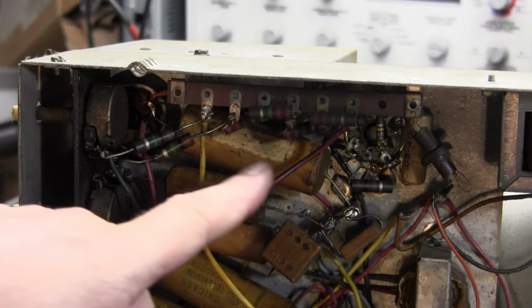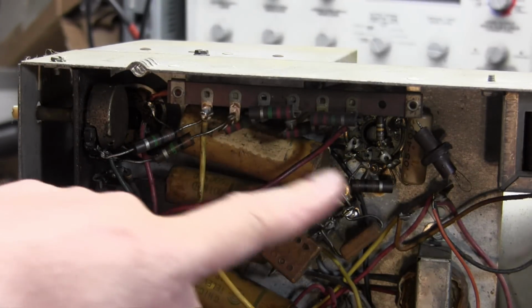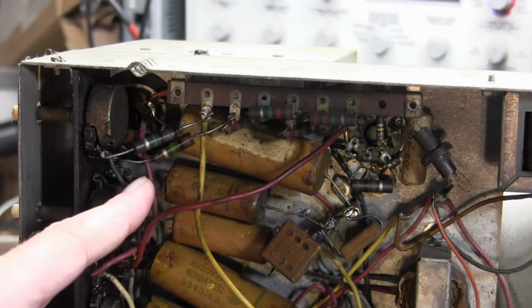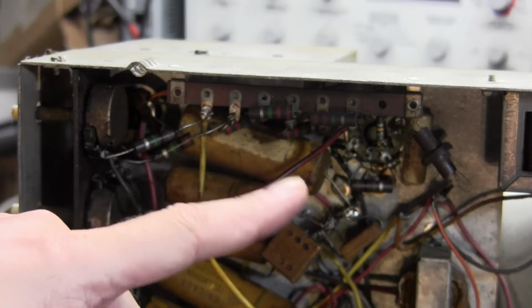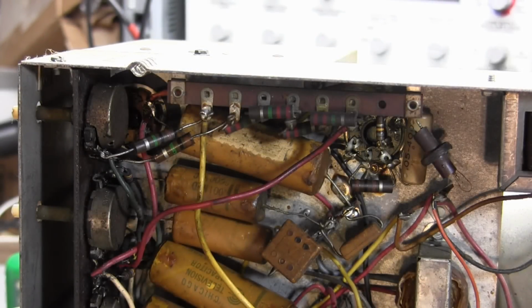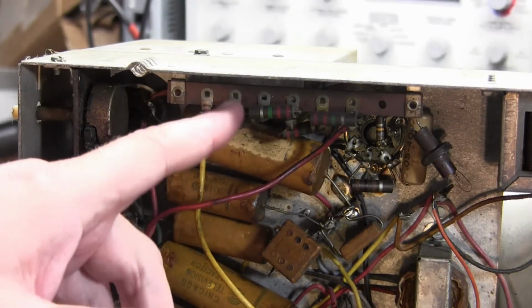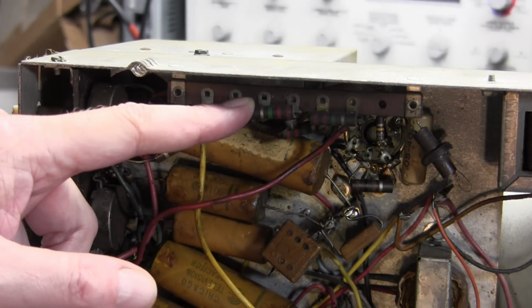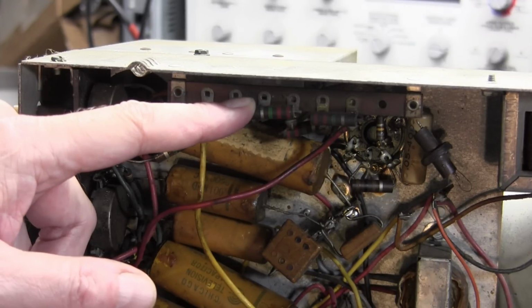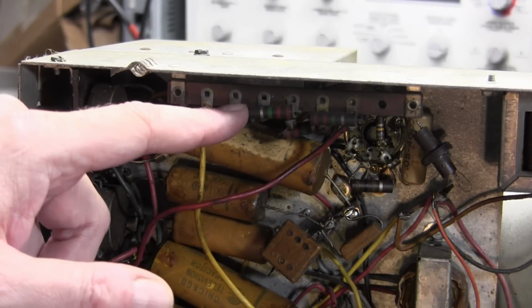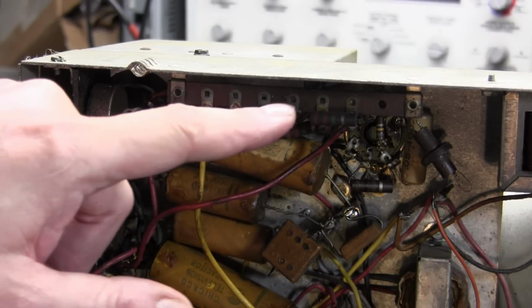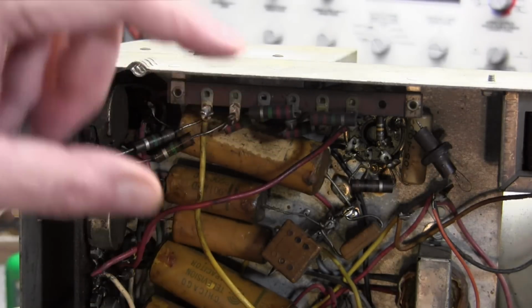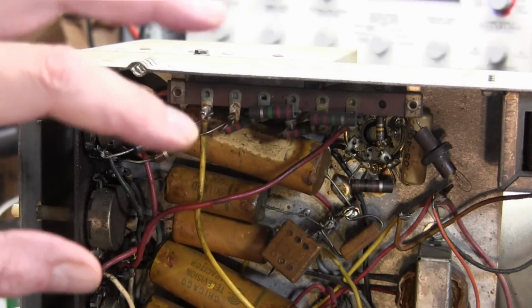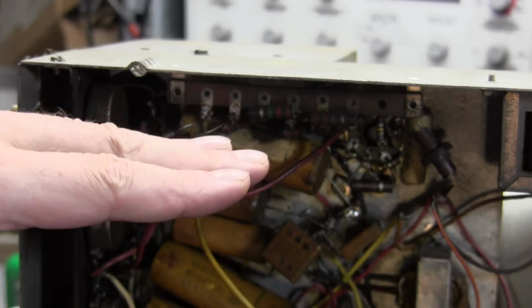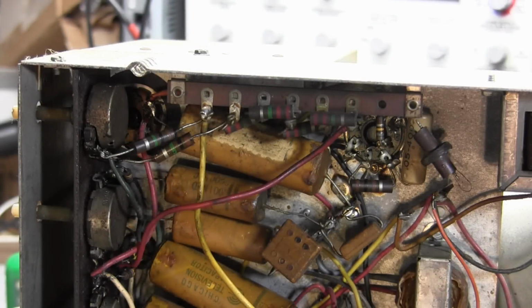We've got around 6 or 7 between 6,000 volts and ground, and if you just do the math, that means we're going to have more than 500 volts across some of these. I've seen these do squirrely things where you can measure them with an ohm meter and it'll measure okay, but when you power the setup, things aren't quite right. I think that's because there are carbon tracks burned into them internally, and when power is applied, it's tunneling through them sort of, messing up the voltage divider.